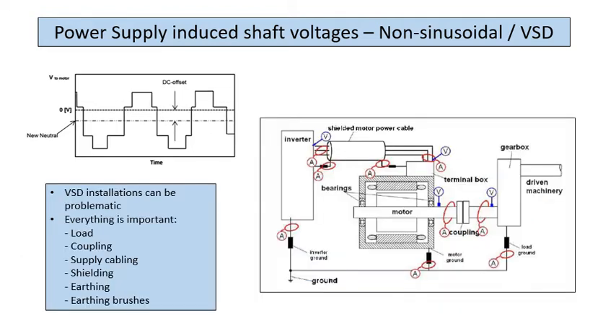Okay. Same thing here. VSD installations, I'm not going to go into, this is a topic on its own, but they can be very problematic. Everything's important: the load, the coupling, the supply cabling, shielding, earthing, and earthing brushes. So the whole lot is, and for example, a good idea is to fit an insulated coupling. And on more than one occasion, we've had a case where a drivetrain has been maintained, and then the coupling insulation has been left out for some reason, and the machines had bearing current issues after that.